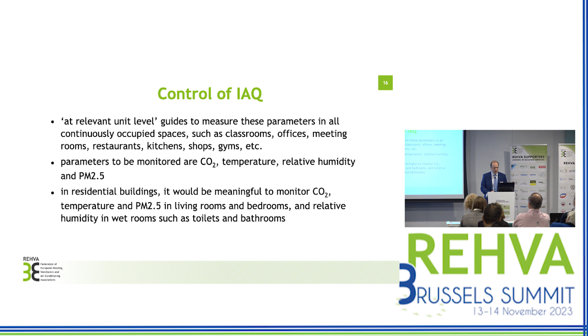And it's slightly different in residential buildings, where it would be meaningful to monitor CO2 and PM2.5 in the living rooms and in bedrooms. Relative humidity would be very important to monitor in wet rooms such as toilets and bathrooms, and there could also be options that this can be done in the ventilation unit. So to set ventilation requirements, we need to distinguish non-residential buildings and residential buildings, and in the standard we have a formula for non-residential where the ventilation rate depends on the number of persons and the number of floor square meters to remove pollutants both from people and from building materials.